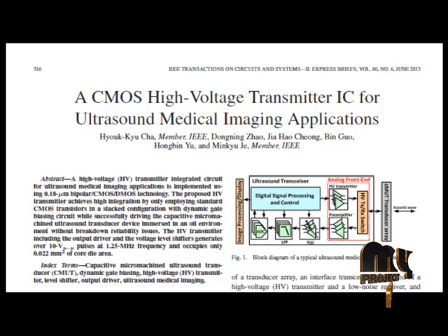In case of a CMUT load, linear amplifiers are not optimum and degrade the overall power efficiency of the transmitter stage. High voltage pulsers can be used instead of amplifiers so that the power dissipated while charging and discharging the capacitance does not contribute to the acoustic output.